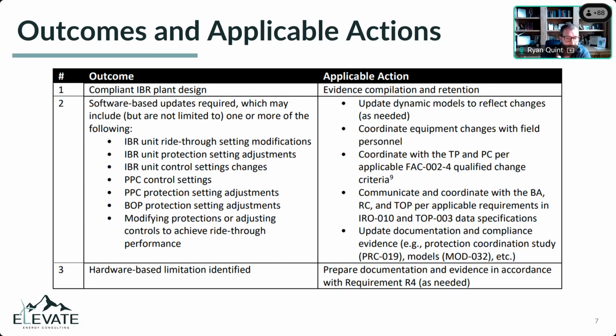You may have to reconduct MOD testing, reconduct PRC-19 protection coordination studies, or update your models. Or you have a hardware-based limitation. In some cases, you can have multiple of these outcomes - a portion of the plant may have a hardware-based limitation, another portion may have relay settings that need to be modified. These are not mutually exclusive. In those cases, you'll be preparing documentation and evidence in accordance with requirement 4 regarding those exemptions.